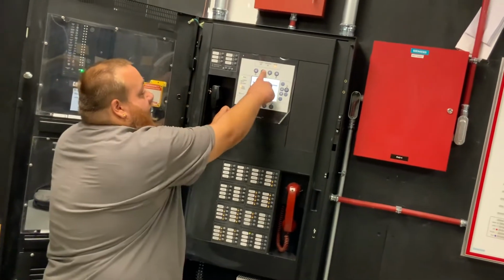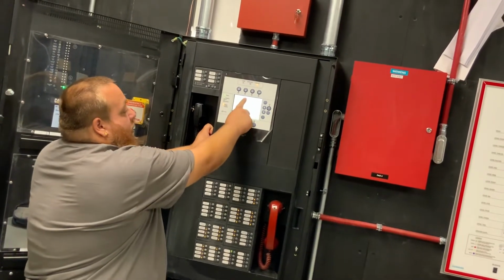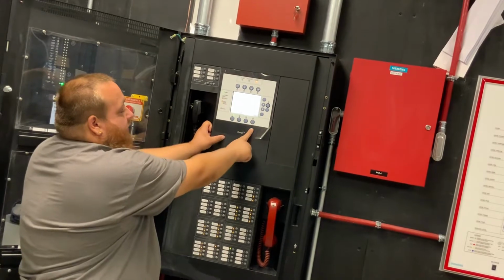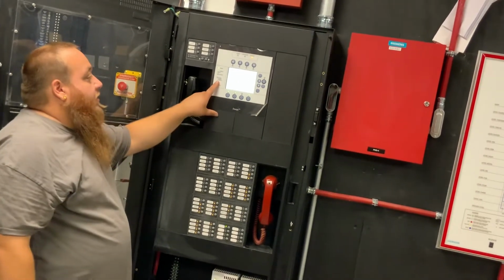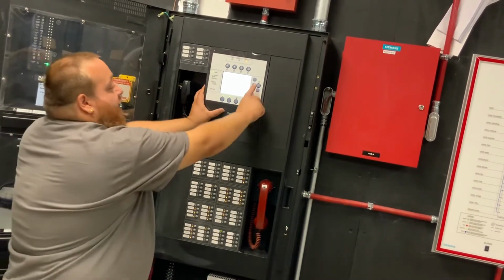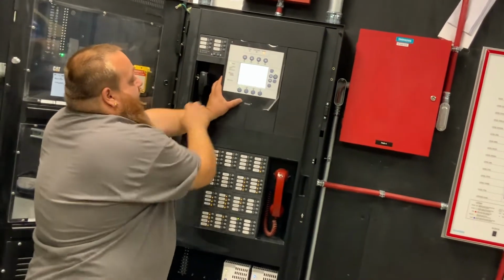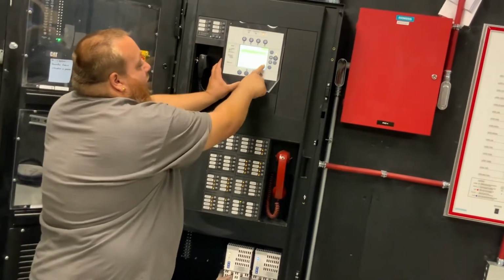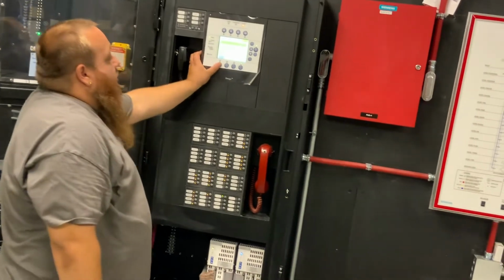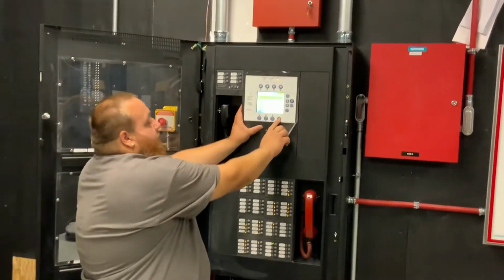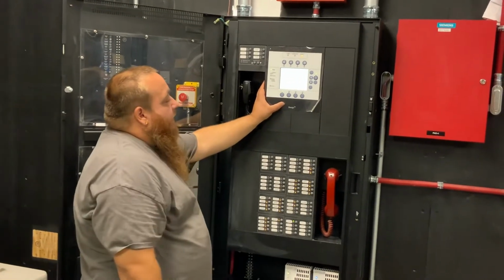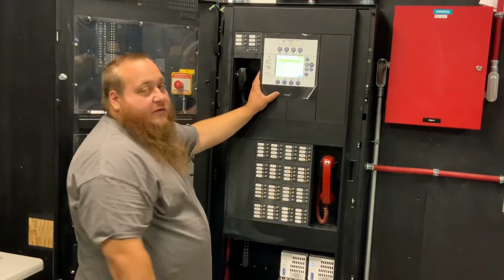So you would simply go back to control. You would arm your device, execute it. You notice disable went out because there's nothing disabled anymore. Back to your menu, and now all your outs will be there. You acknowledge it, change the state, you reset, and now it disappeared.